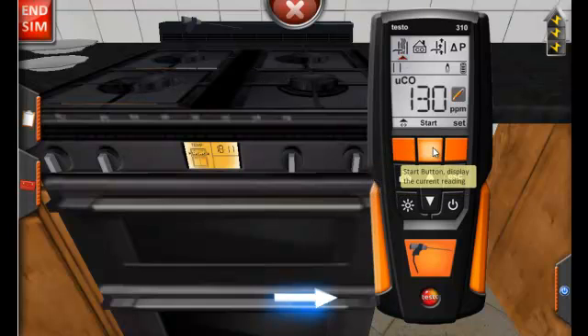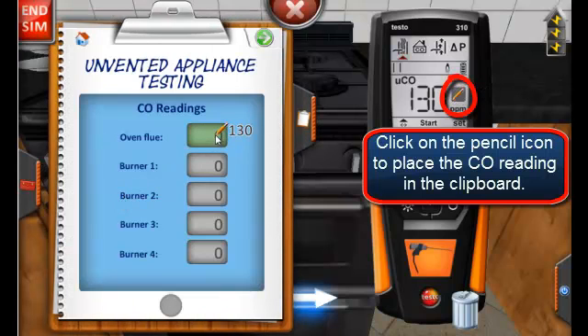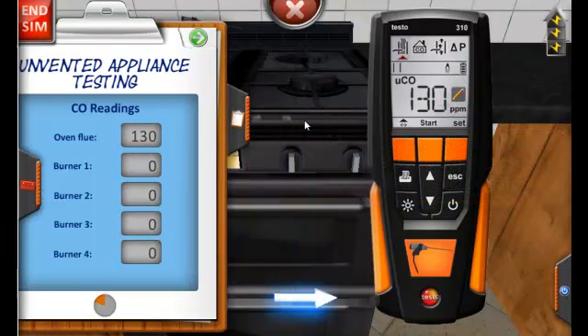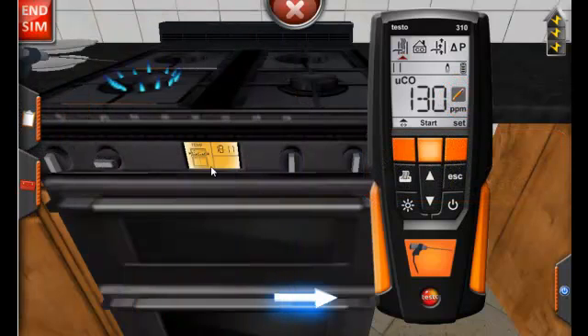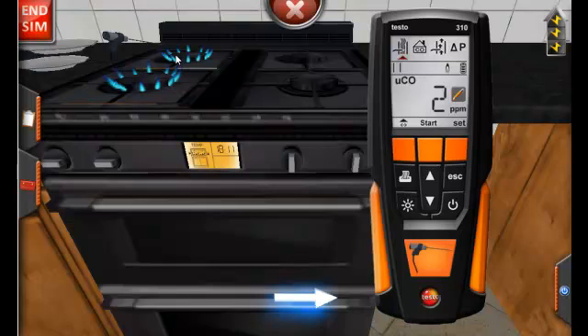Here we see an undiluted CO reading of 130 parts per million. We are going to record that number on our clipboard. We also should test the burners. To do so, we just place the probe above the burner. This first burner gives us a reading of two parts per million, and the same for the second burner. We will record these numbers on our clipboard.